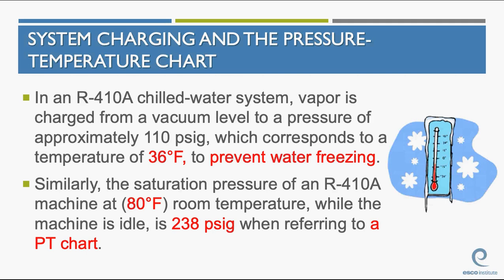Okay, again, the saturation pressure of 410A in a machine at 80 degrees Fahrenheit, at room temperature while the machine is not running, is about 238 psi when referring to a pressure temperature chart. But again, the most important thing on this slide is that on a chilled water system, we charge with a vapor until we hit about 110 psi, because that's above the freezing point of water. At that point, I can start charging with a liquid.